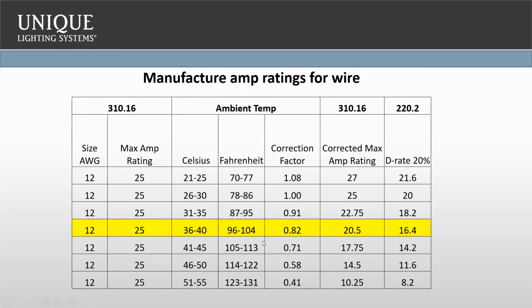If you're in cooler territories and you're never going to hit that 100-degree range, trust me, I can tell you there's times when it's still 100 degrees at 10 o'clock at night here in Arizona. But if you're not in there, then you can give yourself a little bit more wiggle room on the amps. Now, again, I don't expect you guys to memorize this or go through it. If you're at that general 20% D rating off of the manufacturer's recommendations, you're going to get pretty close.